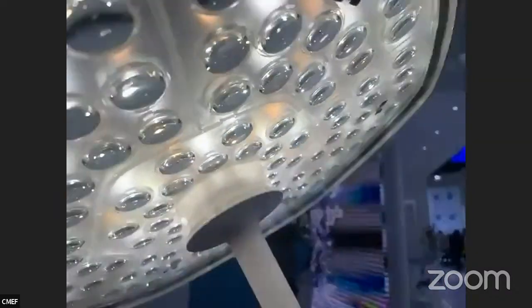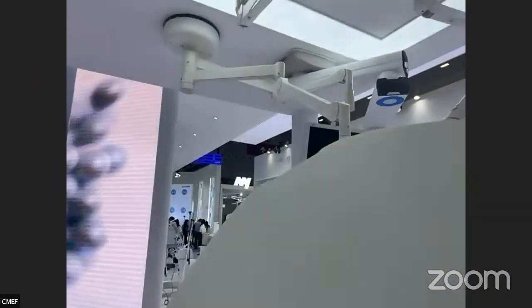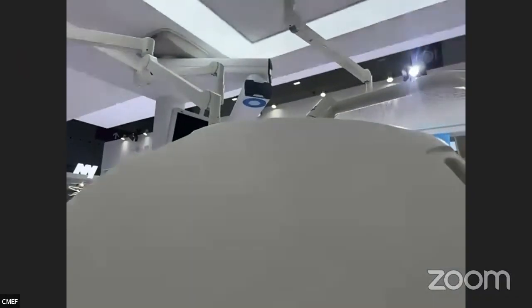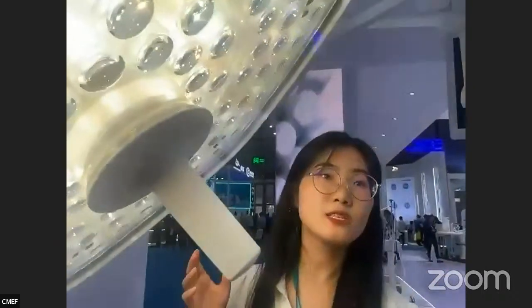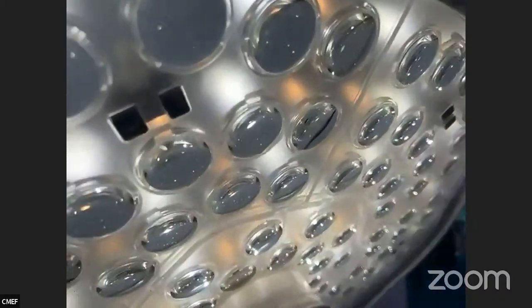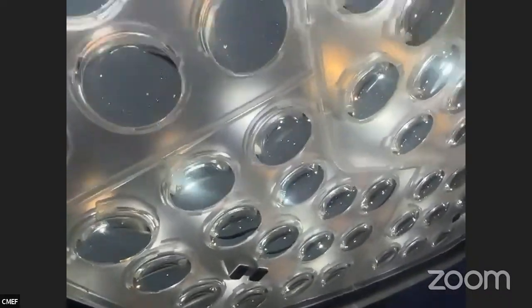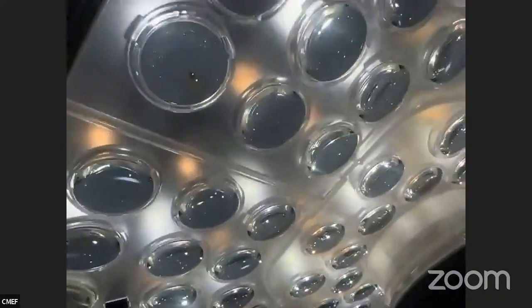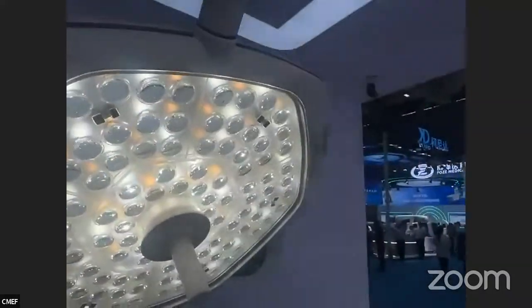The light head adopts a streamlined design, which can meet the laminar flow purification requirements of the operating room, and it also adopts a modular design. We can see here it is divided into 7 parts, and each part is independent from the others. When one is broken, the others can still be used normally. The light spot diameter can reach up to 500 millimeters, which is very suitable for large area debridement surgery.